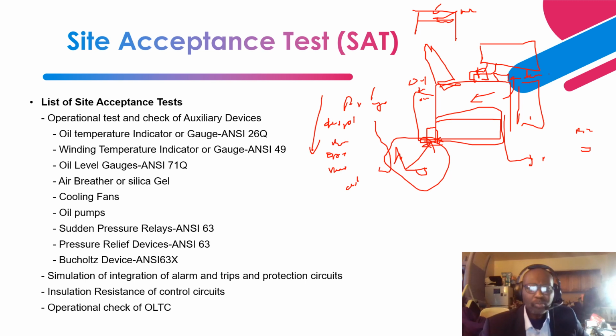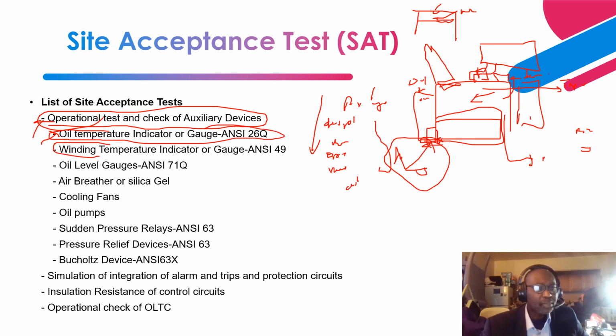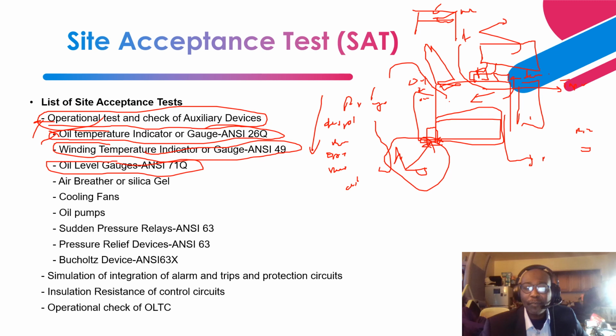Once this transformer is installed, next what you need to do is first do operational tests and checks of the auxiliary devices. And these are the auxiliary devices: the oil temperature indicator, which is looking at the top oil temperature. You do an operational test and check. Then similarly for the winding indicator, you do that to determine the hottest spot. Then all the oil level gauges. We'll have an oil level gauge for the main tank, and also for the conservator tank, we'll have an oil level gauge for it.